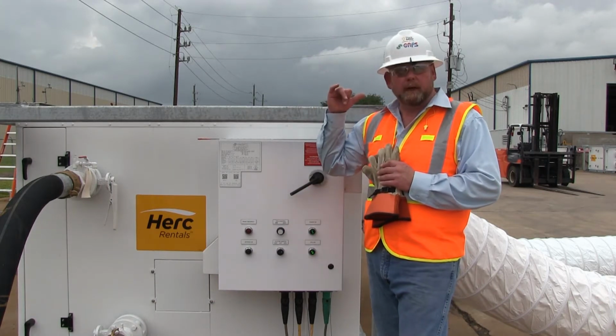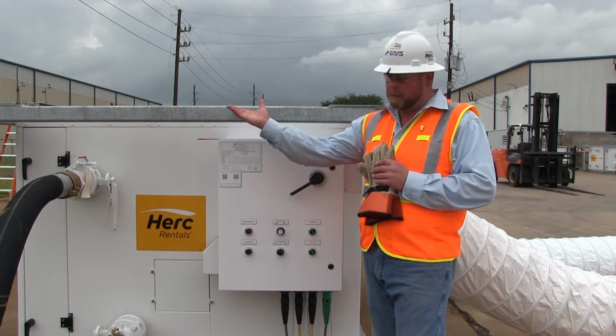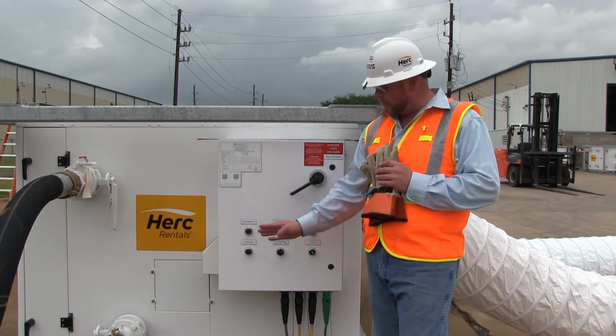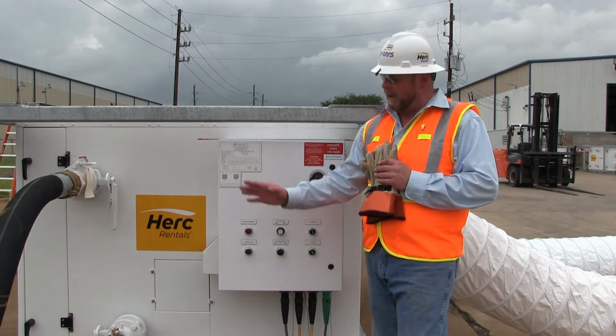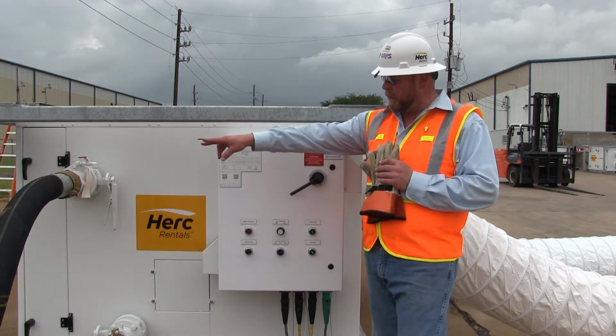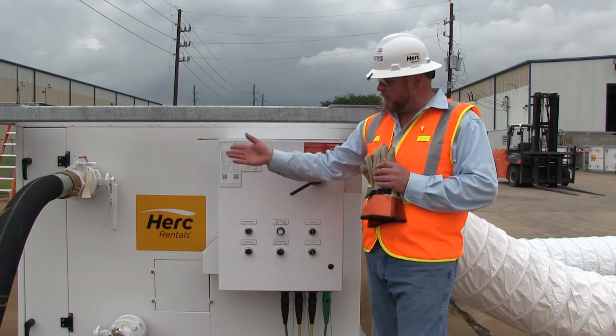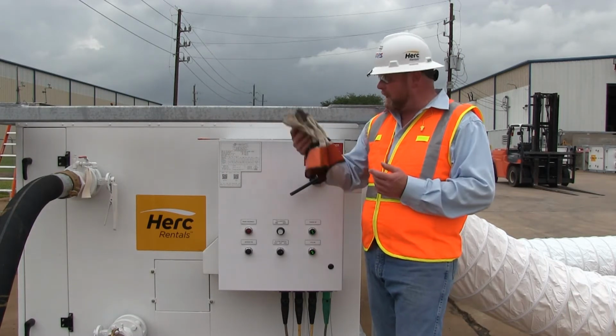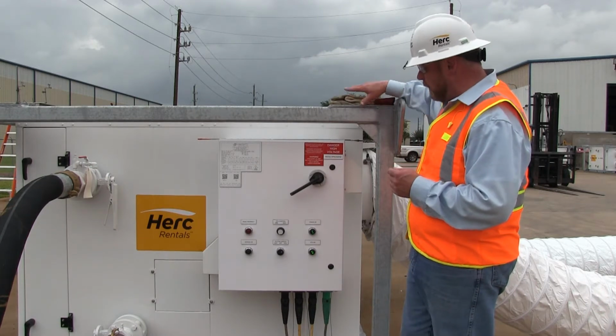We've hooked up our ductwork to our supply. We're in a 100% outside air application. We've primed our condensate trap, and finally we filled up our chill water lines going to the coil, and we've bled all the air out. So the next step is we don't need our gloves anymore. The rest of this is all finger safe.